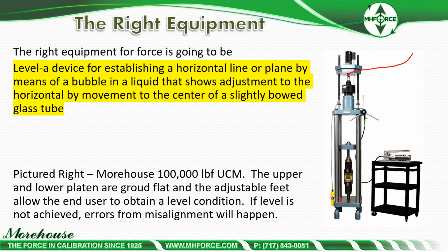Look at here. We calibrate this with a ball adapter, and there we have a ball adapter in use. So, replicating how it's being used, this load cell comes to us and we calibrate it with these exact adapters. That gives you an expected performance. You put it in this machine, and after you put it in this machine, you can do your R&Rs, everything else. But what's brilliant about this machine is it free floats. It has this ball and this yoke, so it has some automatic self-alignment in it. It's just really a cool design. When you machine stuff, you can never get everything perfect. It takes a lot. Almost every machine has some type of misalignment in it. This machine acts better, as is, with that ball, as it helps find center.